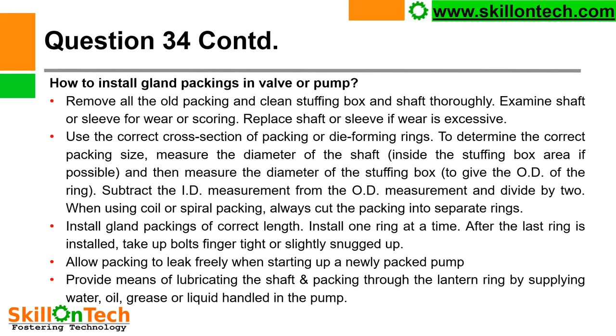How to install gland packing in valve or pump? First of all, remove all the old packings and clean stuffing box and shaft thoroughly. Examine shaft or sleeve for wear or scoring. Replace shaft or sleeve if wear is excessive. Use the correct cross section of packing or die forming rings. To determine the correct packing size, measure the diameter of the shaft inside the stuffing box area and then measure the diameter of the stuffing box to give the OD of the ring. Subtract the ID measurement from the OD measurement and divide by 2. This will give you the size of the gland packing.